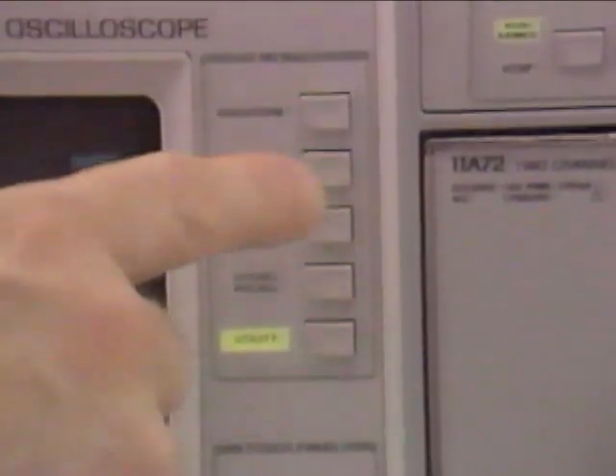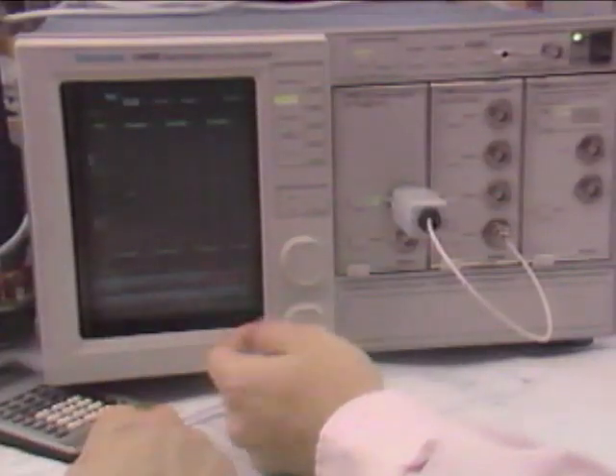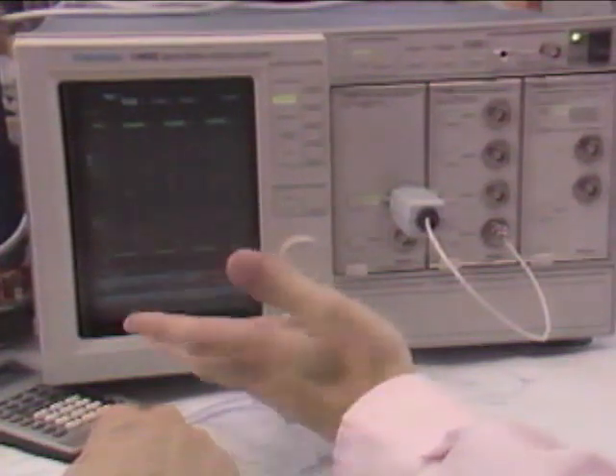Now, how does that help me when I reach for the volts per div knob and find it's not there? Oh, it's there, all right. Right before your eyes. Here, pick from the menu directory. Say, trigger. And all major settings and readouts appear at the bottom of the screen. Readable at a glance. Let's see. Trigger, select, source, level. Now, what's this main size and window holdoff stuff? Well, that's referring to the main and the window records. Now, you can use the 11403 dual time bases, like a delayed sweep function in analog scopes, to create dual windows on the main trace. Except here, of course, you get pre-trigger data, too. Yeah, that's all pretty clear.